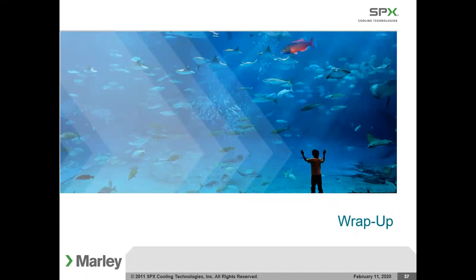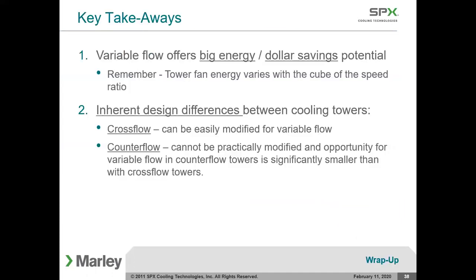Okay, wrap up. We're just about finished with this. Variable flow offers big energy and dollar savings potential. Fan energy varies, not really quite with the cube of the speed, but pretty close. There are inherent differences between cross-flow and counterflow towers. Counterflow, it's hard to modify much in terms of water flow rates. The cross-flow, it works pretty well.